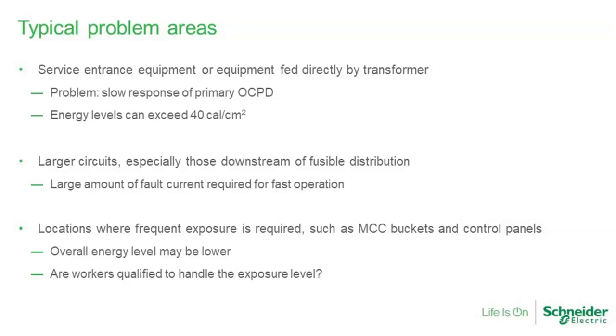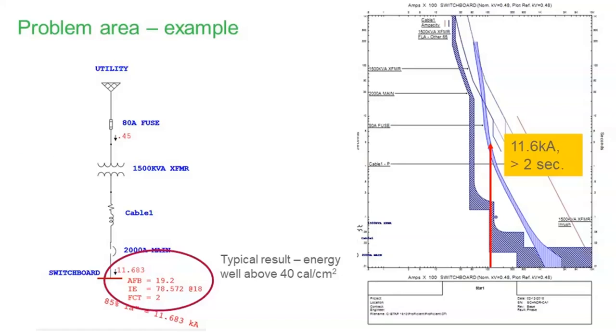Other problem areas, and we'll talk about this a little bit more when we get to looking at our strategies, but maybe a problem area is not where energy is the highest, but maybe it's where exposure is more frequent, such as MCC buckets or control panels. You know, we might have very high energy levels at the service entrance equipment, but realistically, on a day-to-day basis, electricians are not getting into that equipment. It's just something they don't interact with very much, but they're having to get inside control panels or MCC buckets almost on a daily basis to troubleshoot or reset something. Maybe we need to look at those as well. And again, we'll develop that in a little bit more detail as we continue through this.